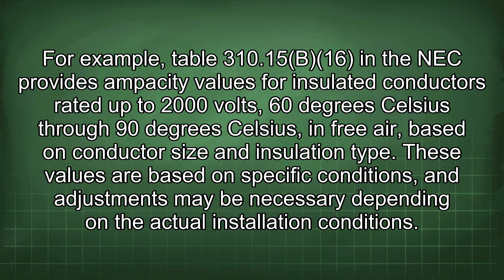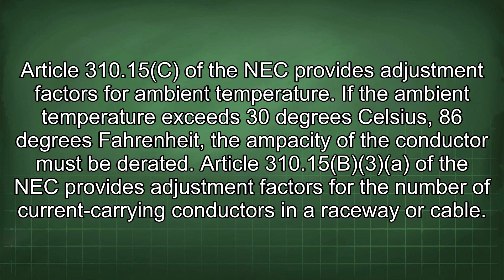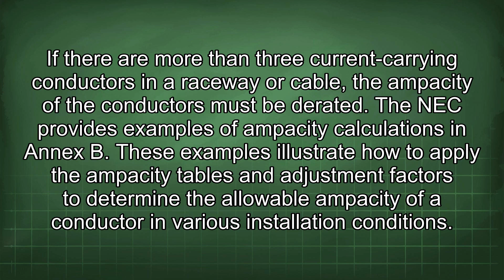Article 310.15(B)(3) of the NEC provides adjustment factors for the number of current-carrying conductors in a raceway or cable. If there are more than 3 current-carrying conductors in a raceway or cable, the ampacity of the conductors must be derated. The NEC provides examples of ampacity calculations in Annex B. These examples illustrate how to apply the ampacity tables and adjustment factors to determine the allowable ampacity of a conductor in various installation conditions. Always consult the latest edition of the NEC and any applicable local codes for the most up-to-date requirements.